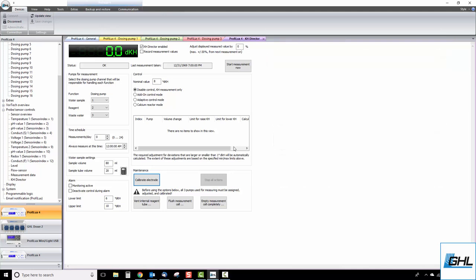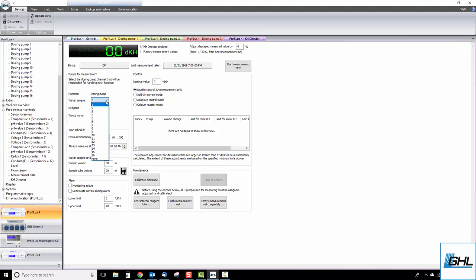Now we get to the part where we configure basic KHD test settings, starting with assigning dosing pump channels to specific KHD functions. Under the Pumps for Measurements section, select the dosing pump channel you want to use for your water sample. For example, we used dosing pump number 1 as our water sample pump, so we'd select dosing pump 1 for the water sample function.